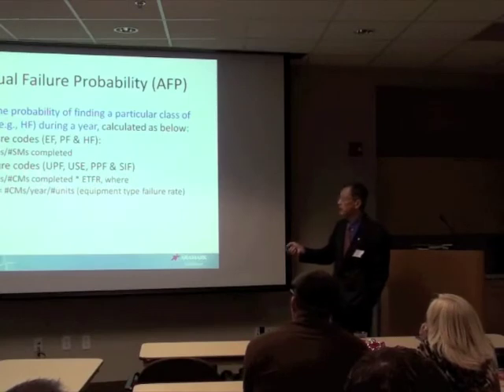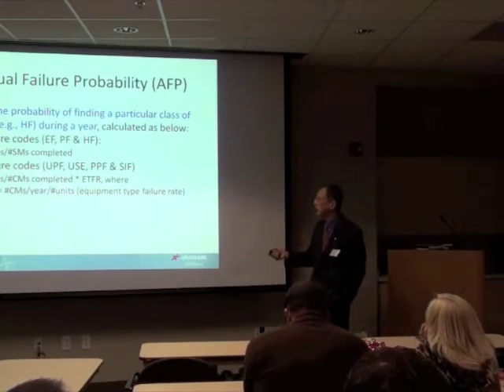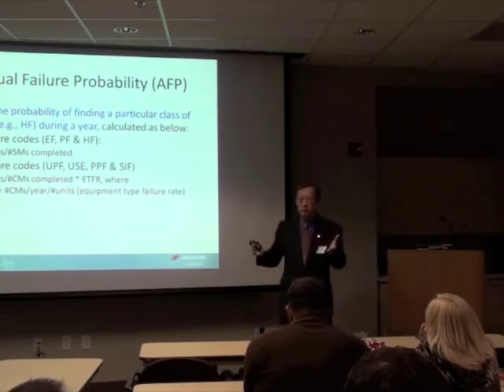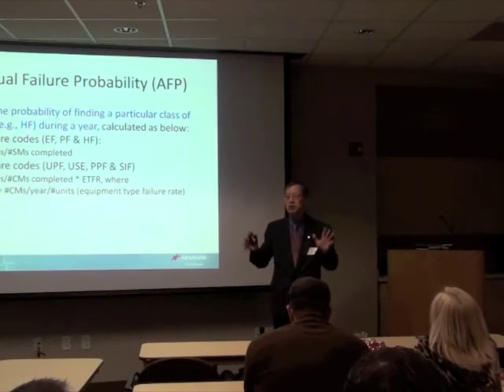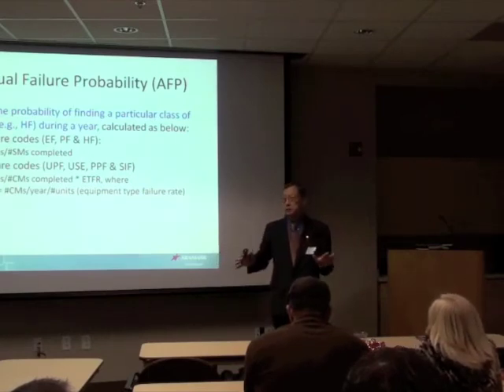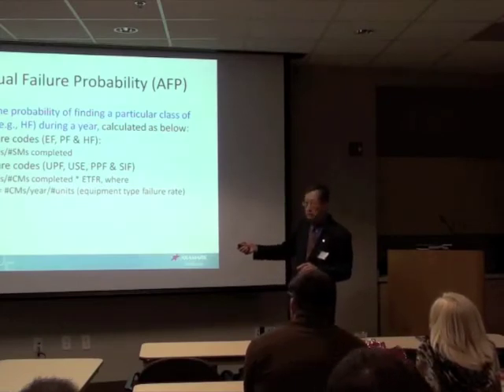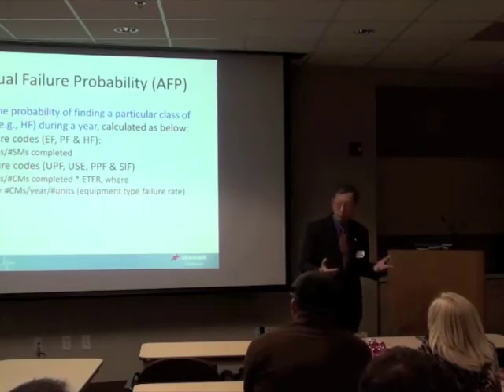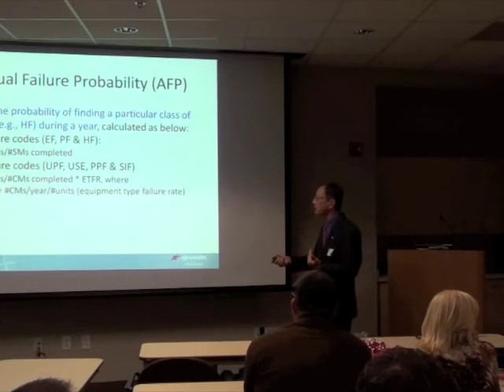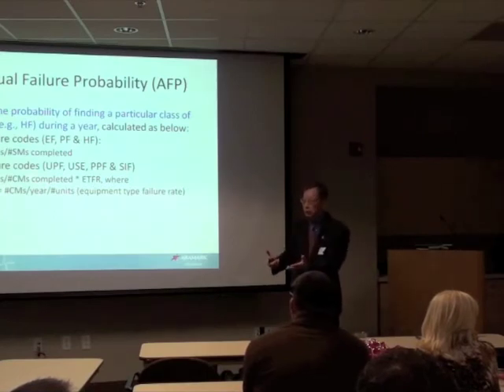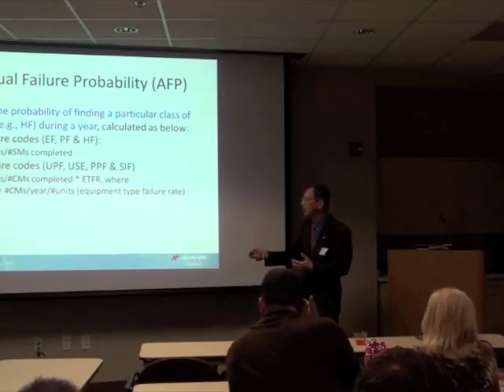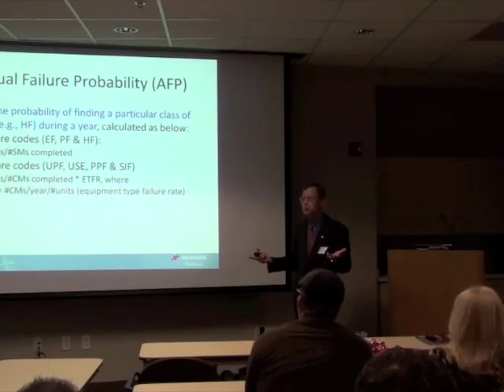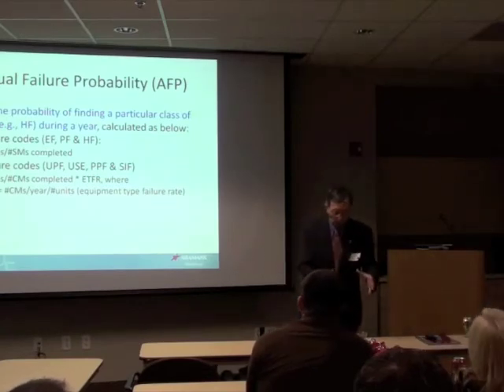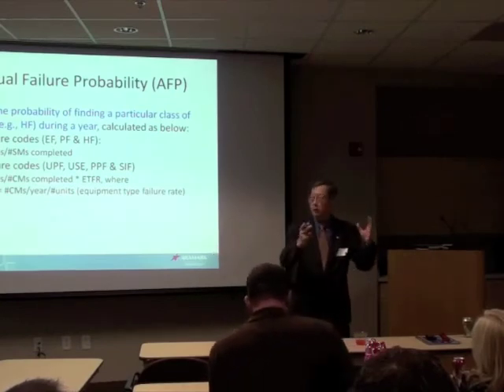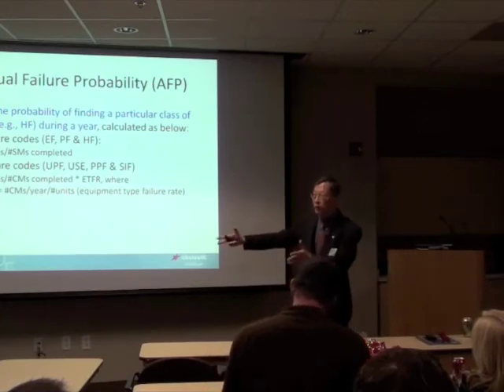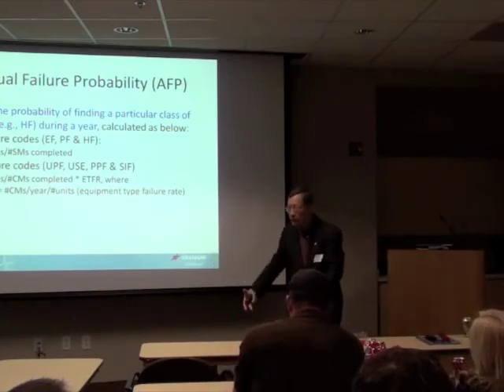But failures found during repairs have to be adjusted by a factor. For example, if infusion pumps are scheduled for maintenance once per year for every device and you never miss it, then scheduled maintenance statistics are exact. However, not every infusion pump gets called in for repair, so you can't say the number of codes divided by number of repairs completed is exactly your failure rate — you have to multiply by the number of units you have during the year. Otherwise you're being unfair, saying 50 of 100 pumps failed and only counting the 50, when the other 50 should still count, dropping the rate to half.